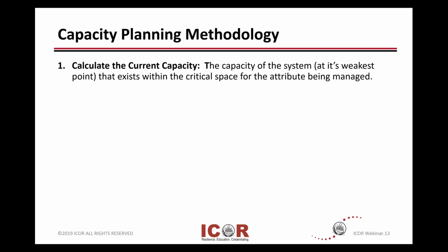Efficiency - when you look at electrical and mechanical devices, simply said, your mechanical and electrical devices, whether it's a generator or an HVAC unit, are at their most efficient when they're running full out, at 100% capacity. If you're dealing with high availability and a redundancy situation, you'll never achieve that, or you don't want to achieve running at 100% capacity.